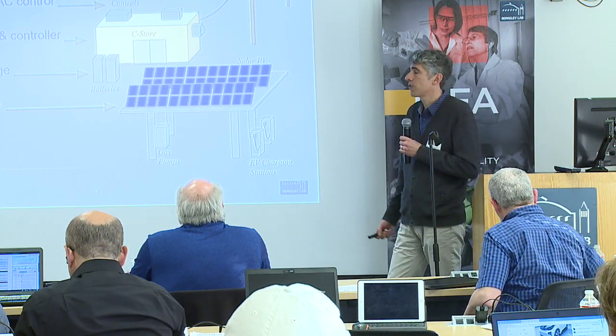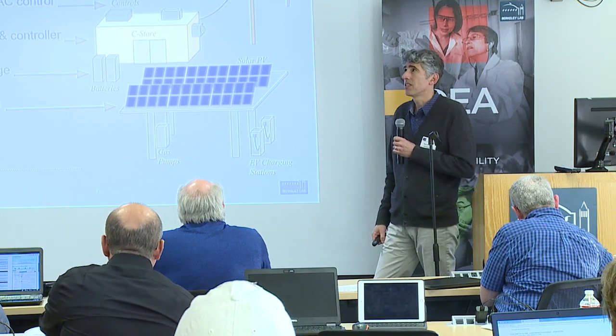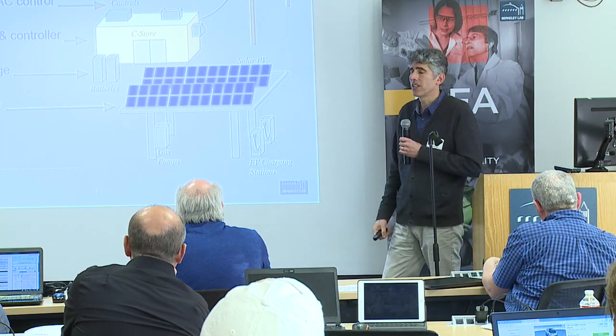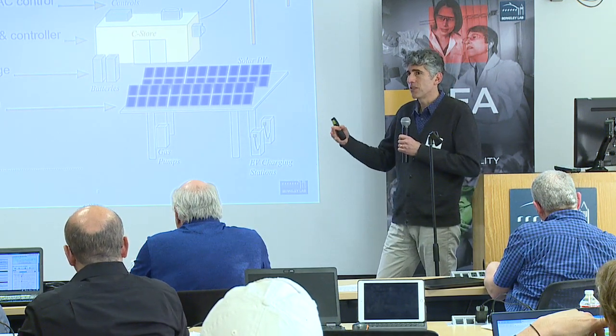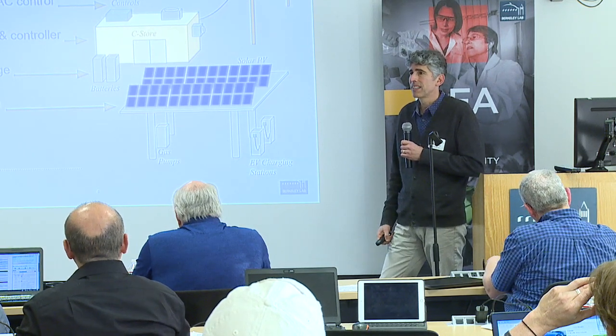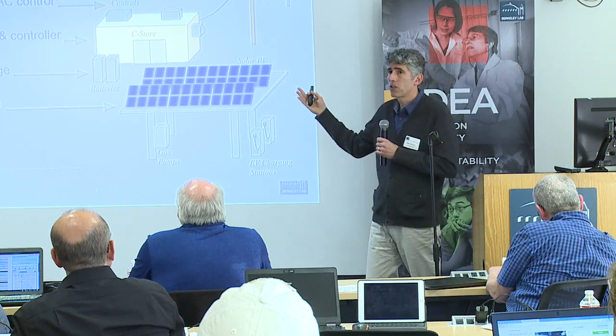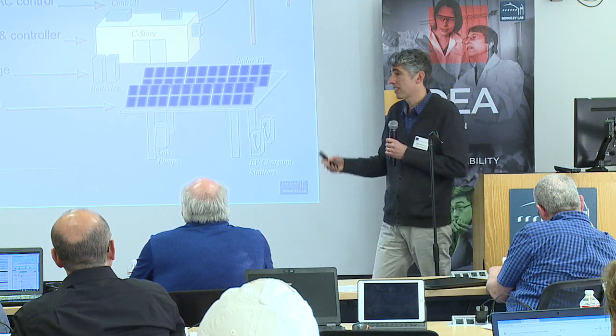Yeah. And then the other issue is defrost, actually. So the defrost cycle runs, I think, every 6 hours. And that's a pretty significant spike, but it's not thermostatically controlled like the compressor is. So in terms of modeling it and actually developing a model of the physical system, that's kind of a challenge, that the defrost heaters run on a different cycle. But that's the idea, basically: using either the building itself, or in the case of the refrigerator freezer, the product as energy storage that you can use to shift loads. That's kind of the basic idea.